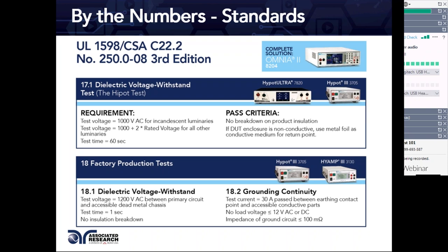The 60-second Hypot test indicates this is most likely a design or type test. For pass/fail criteria, the standard says no breakdown of product insulation shall occur. That's somewhat vague — it means as long as insulation isn't breaking down, the product complies. A 60-second test is characteristic of a design test rather than a production test.